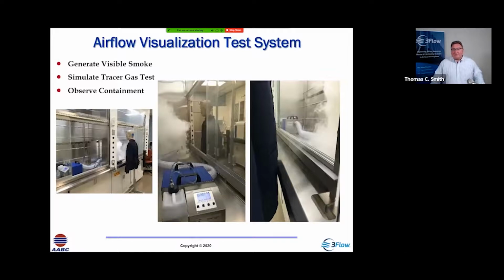Now there's other types of generators. In this case, we have a fog generator that was built especially for conducting fume hood tests. You put a generator inside the hood, a diffuser, and you generate the smoke, and you can dial in the quantity, and it'll continuously produce a visible plume of smoke. And then you can do things like opening and closing the sashes and use a mannequin to simulate a person doing walk-bys and so forth. And this allows you to identify weaknesses in hood performance. And we can see here, because of the aerodynamic design, there's actually escape out of the hood, and that would enable the person to be exposed to exactly what they're trying to protect against.